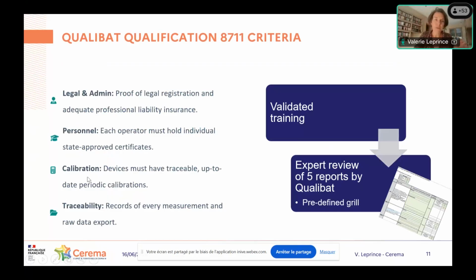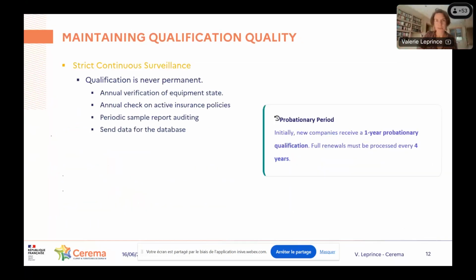The qualification body also checks the calibration of the devices, and they record every measurement and raw data export that is done. I will talk to you about this database. And there is a continuous surveillance, so the qualification is never permanent. There is an annual verification of equipment state, so they have to send their calibration certificate to the qualification body. And sometimes also, after 4 years usually, they check periodic sample reports.